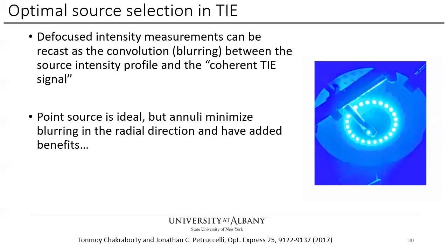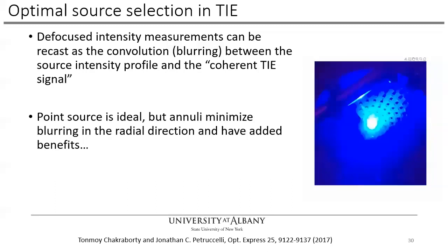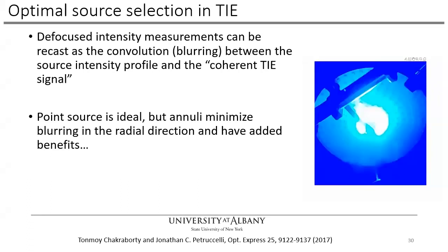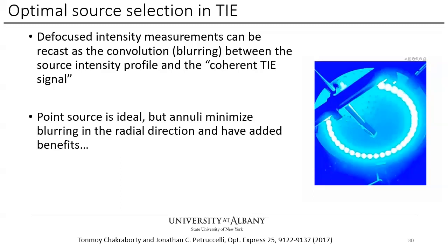So in terms of how we do the sources, I said you could use a standard microscope illumination, and we have in the past. But because we want to boost the resolution and get more light, we're using a programmable LED array. This allows us to change the shape of the pattern with a bunch of little LEDs that we can program how they appear during our measurement. We can scan through a bunch of different patterns. We pick one pattern to do all our measurements with. We don't scan them as we're taking measurements.